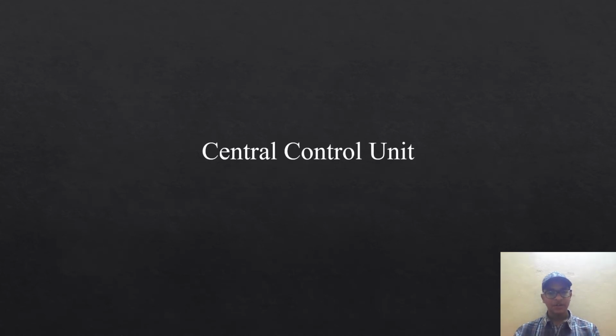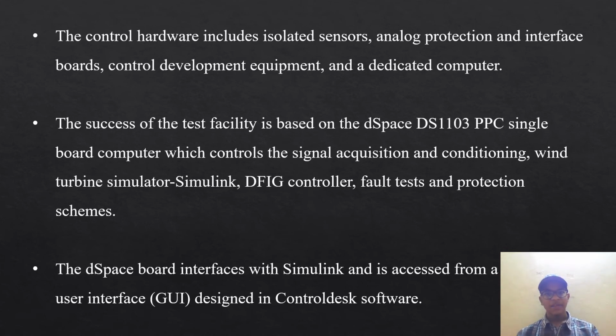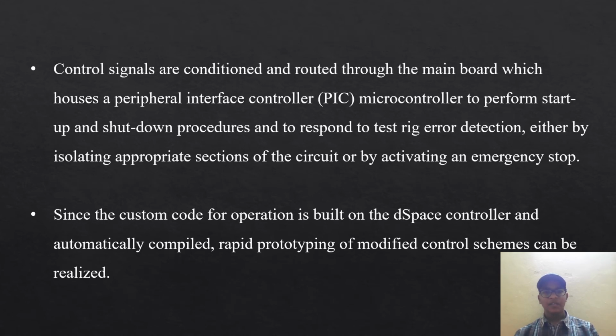Now we are going to discuss the central control unit. The control hardware includes isolated sensors, analog protection with interface boards, control development equipment, and a dedicated computer. The success of the test facility is based on the dSPACE DS1103 PPC single board computer, which controls the signal acquisition and conditioning, wind turbine simulators simulating DFIG controller test, fault test, and protection schemes. Control signals are conditioned and routed through the main board, which houses a peripheral interface controller microcontroller to perform the startup and shutdown procedures and respond to test rig error detection, either by isolating appropriate sections of the circuit or by activating the emergency stop.